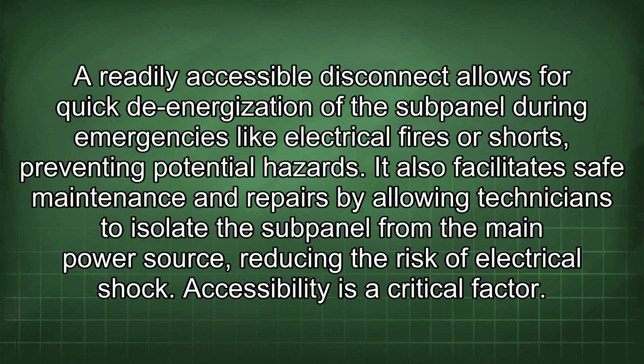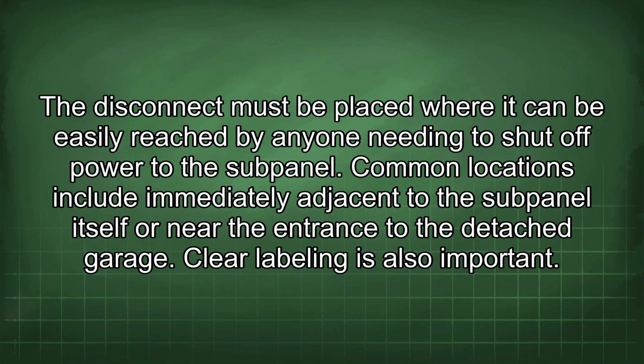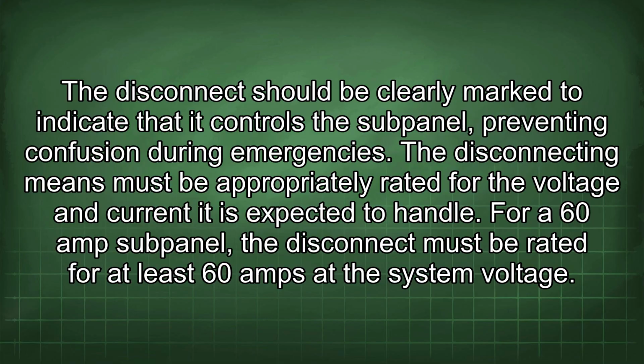Accessibility is a critical factor. The disconnect must be placed where it can be easily reached by anyone needing to shut off power to the subpanel. Common locations include immediately adjacent to the subpanel itself or near the entrance to the detached garage. Clear labeling is also important. The disconnect should be clearly marked to indicate that it controls the subpanel, preventing confusion during emergencies.